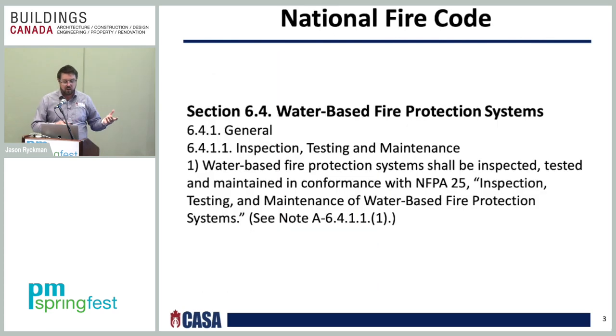So with the National Fire Code, which is used pretty much throughout all of Canada, it is basically a code that references NFPA 25 as the sole standard to use whenever you inspect, test, and maintain a system. So in 6411, it basically states that a water-based fire protection system shall be inspected, tested, and maintained as per NFPA 25, which is the inspection, testing, and maintenance standard, which is again referenced in the National Fire Code. So throughout Canada, ultimately you use NFPA 25.